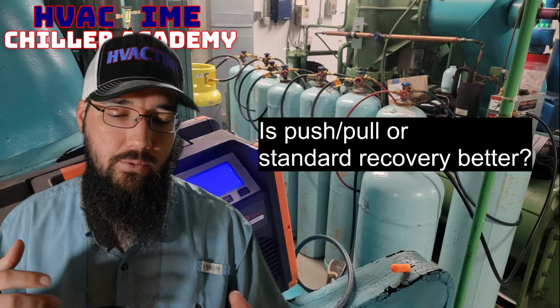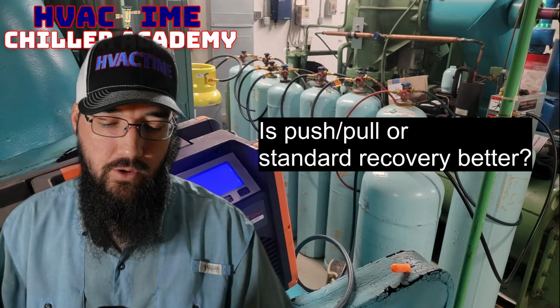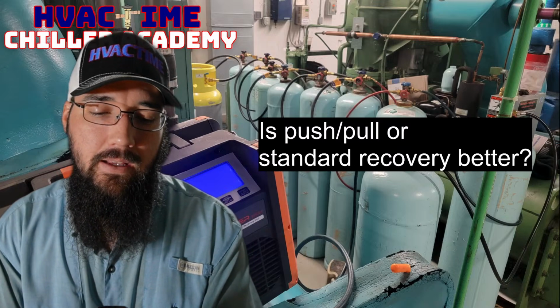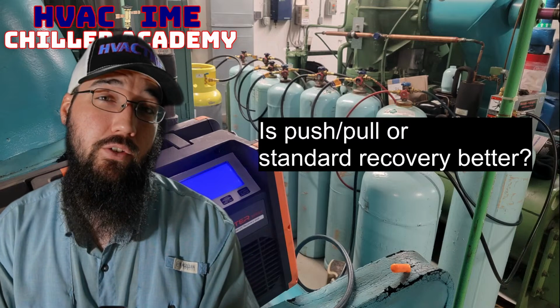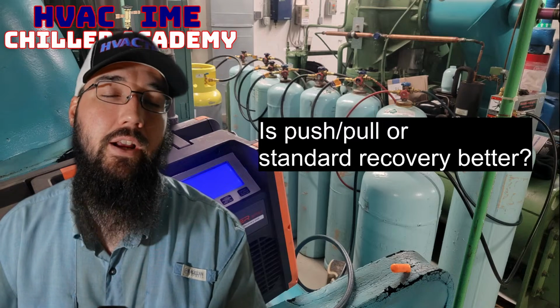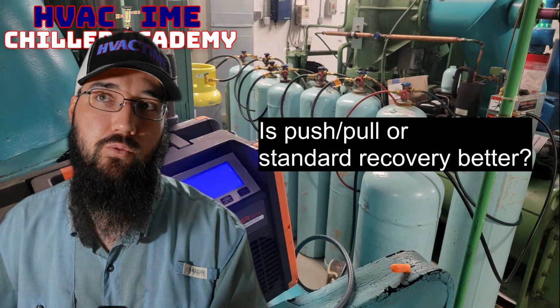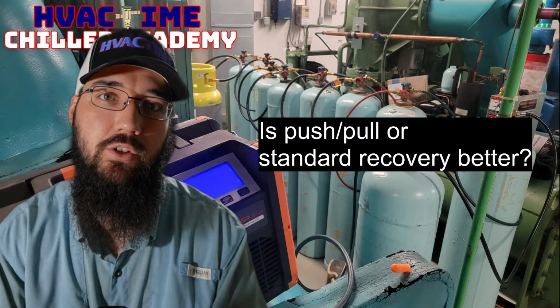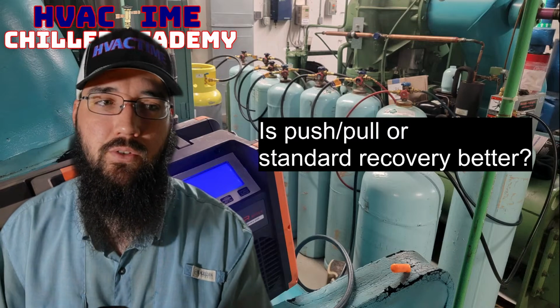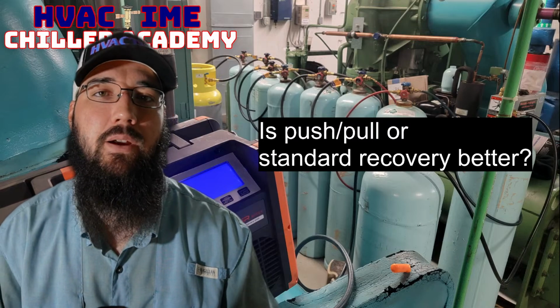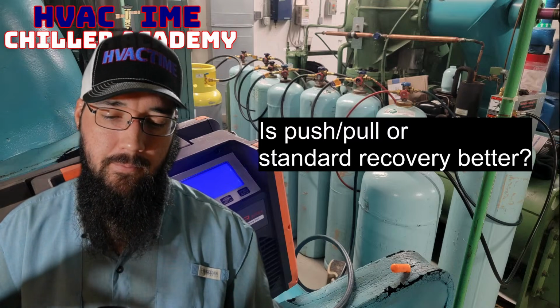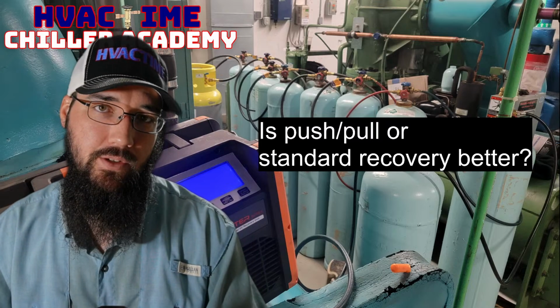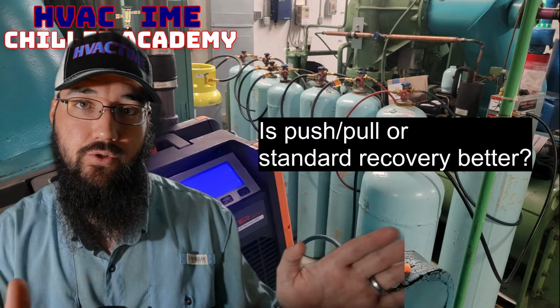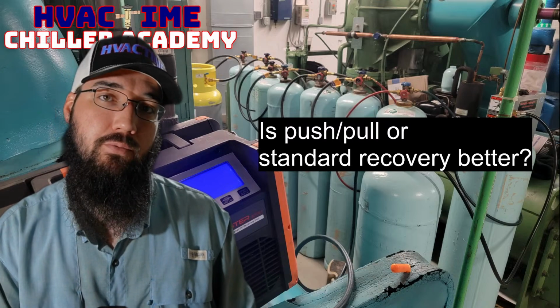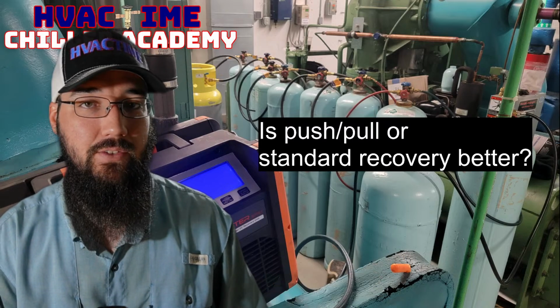I don't want to go too far off on that tangent, but that's a very fast way to move refrigerant directly, where your recovery machine is literally pumping liquid from one place to another to maximize flow rates. Comparing that procedure to push-pull, push-pull is still about twice as fast.